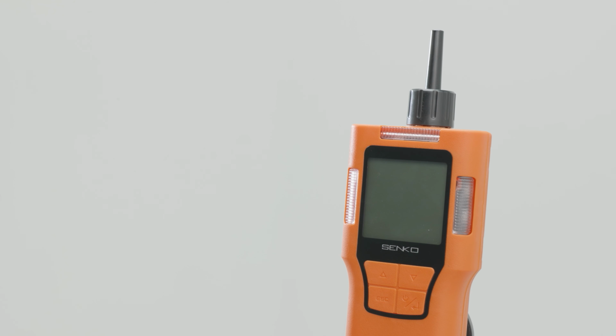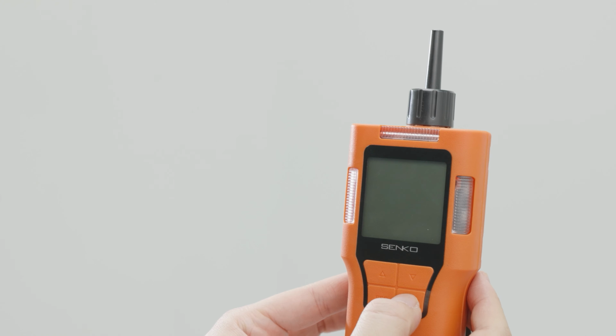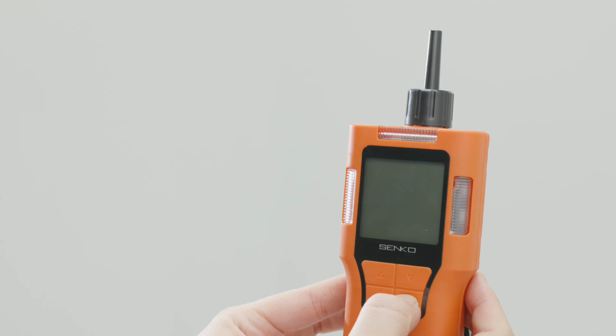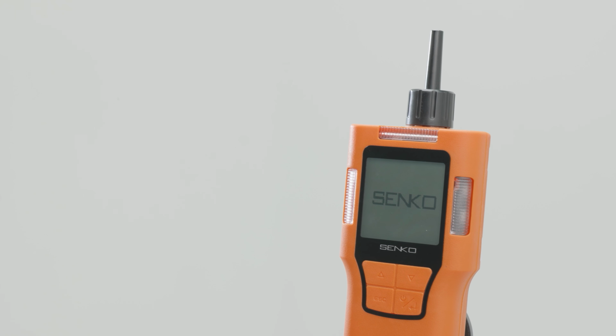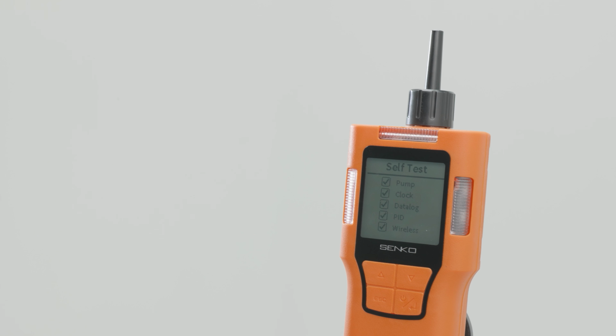Now, let's look at the basic operation of V-Pro. First, how to turn on the power. To turn on the power, press and hold the power input button for 3 seconds. After the Senko logo appears on the screen, a self-test is performed automatically along with device information. When the self-test is completed, V-Pro switches to measurement mode, and the main screen is displayed.